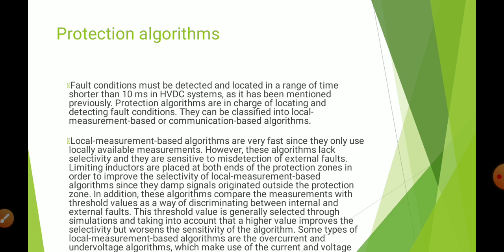Protection algorithms. The fault conditions must be detected and located in a range of time shorter than 10 milliseconds in an HVDC system. As mentioned previously, protection algorithms are in charge of locating and detecting fault conditions. They can be classified into local measurement based or communication based algorithms based on how quick they are. Local measurement based algorithms are actually very fast since they use only locally available measurements. However, these algorithms lack selectivity and they are sensitive to misdetection of external faults.